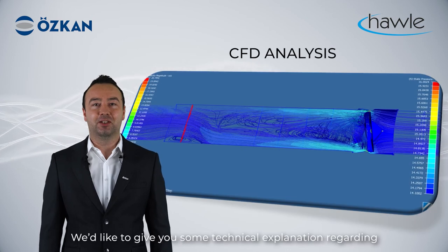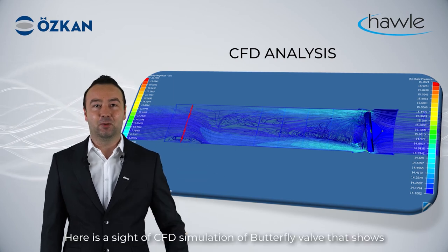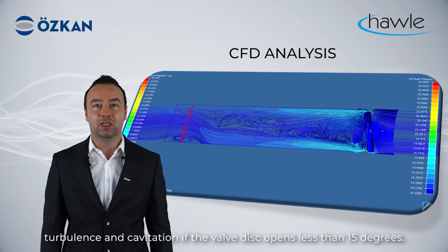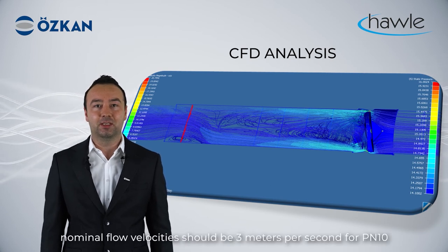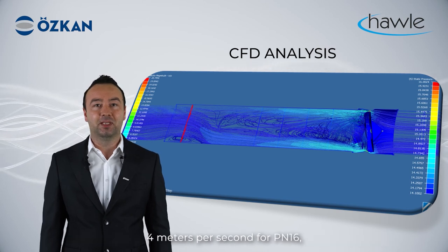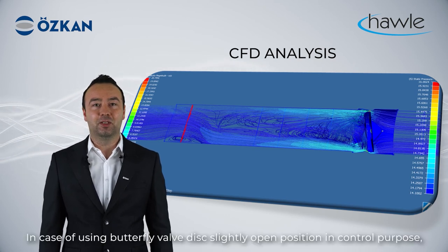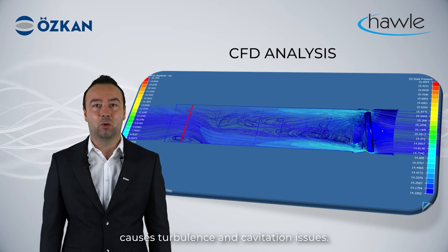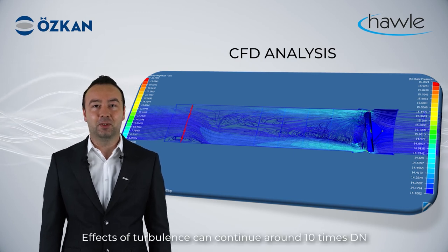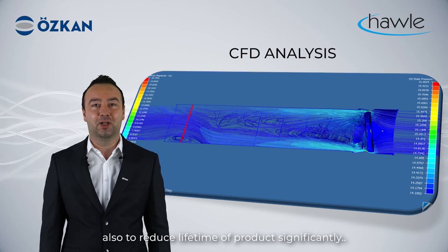We would like to give you some technical explanation regarding why butterfly valves should not be used for control purposes, which is sometimes required by water companies. Here is a CFD simulation of a butterfly valve showing turbulence and cavitation when the valve is open less than 15 degrees. Based on the EN 1074 standard, nominal flow velocities should be 3 m/s for PN10, 4 m/s for PN16, 5 m/s for PN25, and 6 m/s for PN40. In case of using a butterfly valve in a slightly open position for control purposes, nominal flow velocity reaches high levels that cause turbulence and cavitation issues. The effects of turbulence can continue for around 10 times the nominal diameter downstream and could damage all equipment in the pipeline, as well as significantly reducing the lifetime of the product.